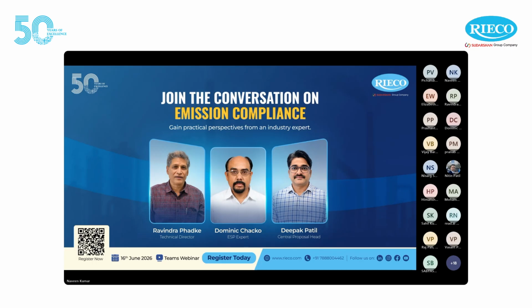Another aspect is any false air leakage happening at the level of the hoppers, that is, the bottom of the ESP, or the conveying mechanisms. Even if that share is very minor, even if it's of the order of 1% or 2% of the gas flow, depending on the location where that leakage is, it can have a serious impact on the emission by way of the phenomenon called re-entrainment of the dust. This can happen more extremely at the last hoppers of the ESP, that is, the outlet side hoppers. If you have some leakages through the outlet hoppers, that dust which is kicked up will not go to the treatment zone of the ESP again, it goes straight to the chimney.